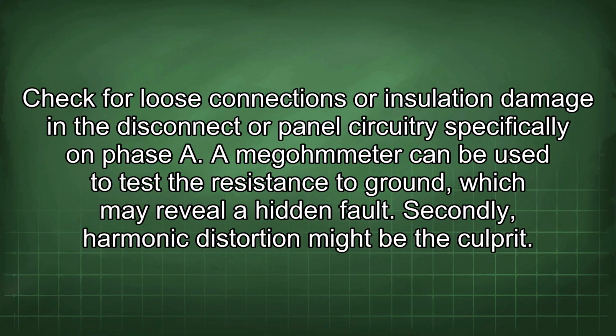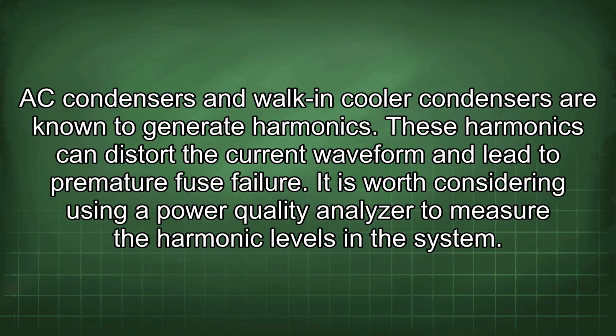Check for loose connections or insulation damage in the disconnect or panel circuitry, specifically on phase A. A megohmmeter can be used to test the resistance to ground, which may reveal a hidden fault. Secondly, harmonic distortion might be the culprit. AC condensers and walk-in cooler condensers are known to generate harmonics. These harmonics can distort the current waveform and lead to premature fuse failure. It is worth considering using a power quality analyzer to measure the harmonic levels in the system.